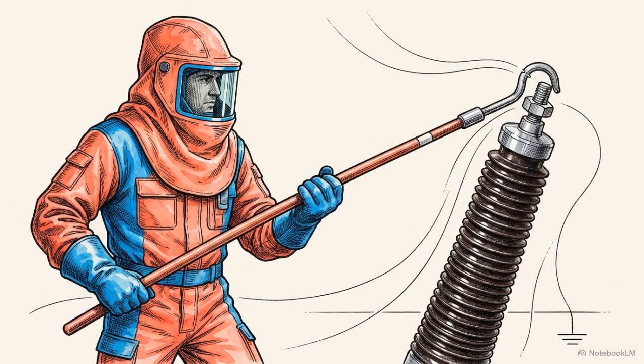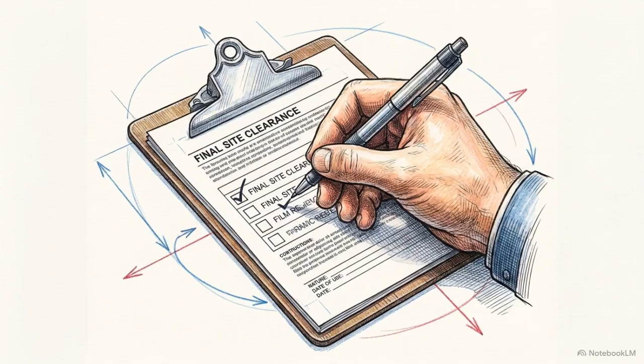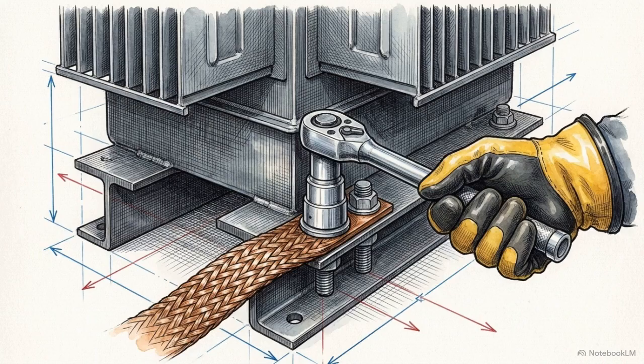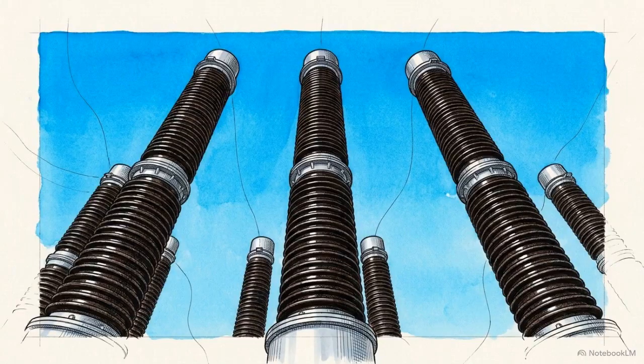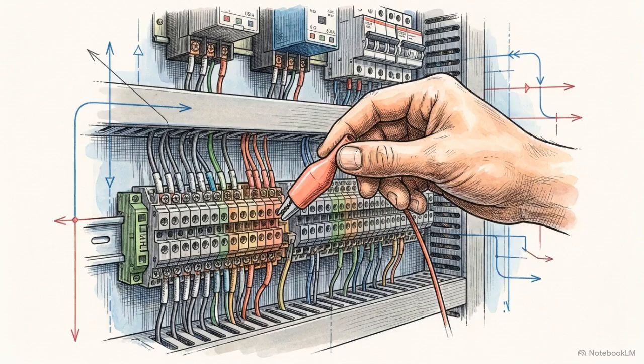Once testing concludes, the as-left restoration protocol begins. The core and frame ground links that were removed for 1 kV testing must be bolted back into their original documented positions. The commissioning team must then physically walk the perimeter, executing a visual verification to guarantee all heavy temporary shorting links and test jumpers are entirely removed from the bushings. Inside the marshalling kiosk, every temporary override, forced sensor signal, and protection trip block used during functional testing must be cleared and rearmed.